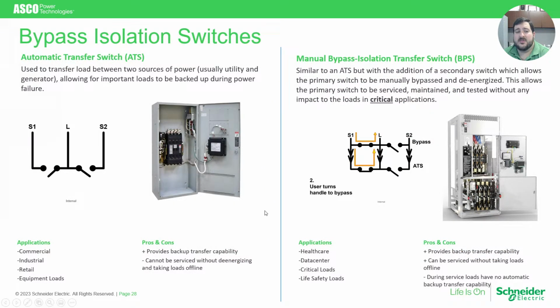We've been talking a lot, and I've been focusing around automatic transfer switches, which you can see here on the left-hand side. But there is another style of transfer switch that also falls into our 7000 series, which is a bypass isolation transfer switch. Bypass isolation transfer switches are almost like two transfer switches in one that go into ultra high reliability applications such as healthcare, data center, supercritical loads, where you want to be able to have a way to bypass the primary ATS to do service, but you can't afford to take your loads offline to do that service. So a standard ATS, to service it, you most likely have to take it offline, which means your loads have to go offline. But in applications such as a hospital, you can't afford to do that.